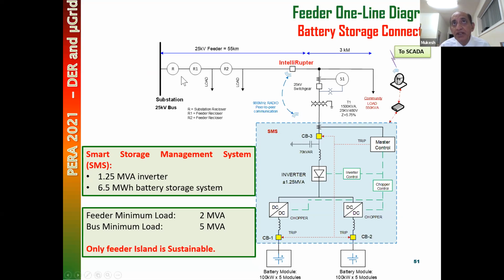We put a PD here, we put a new protection here, and there are feeder reclosers here. And this is our inverter. This is our inverter connected to this feeder through a delta-star transformer. This side is delta, this side is Y grounded. Now, Y grounded, solid grounded, because this is 55 kilometers long here, and this source is relatively strong.